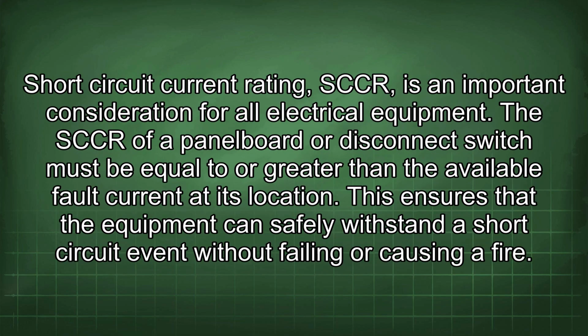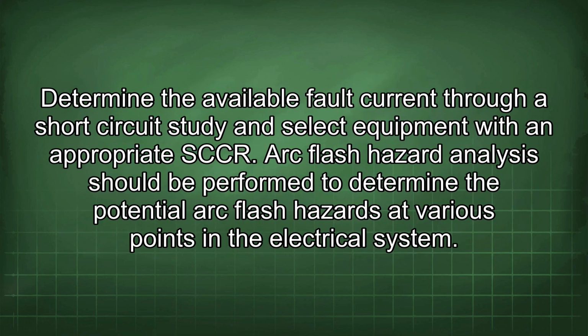Short circuit current rating, SCCR, is an important consideration for all electrical equipment. The SCCR of a panel board or disconnect switch must be equal to or greater than the available fault current at its location. This ensures that the equipment can safely withstand a short circuit event without failing or causing a fire. Determine the available fault current through a short circuit study and select equipment with an appropriate SCCR.